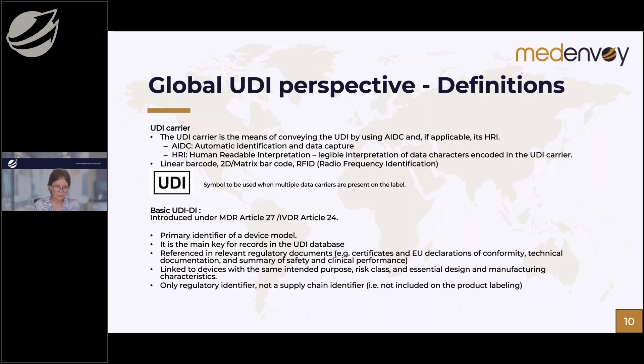So looking at the basic UDI-DI, the concept introduced with the MDR, that's a regulatory identifier. It's not part of your labeling. It's a key to records included in the UDI database in EUDAMED, and it clusters devices with the same intended purpose, risk class, essential design, and manufacturing characteristics. And it will end up on regulatory documents like your declaration of conformity, certificates, and on specific tech file documentation as well.